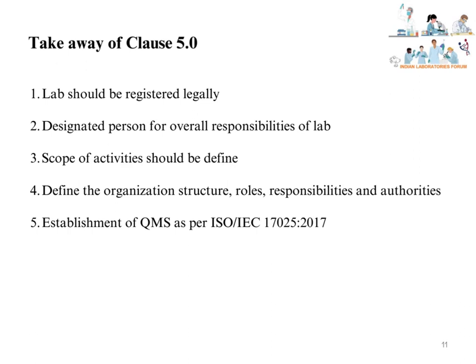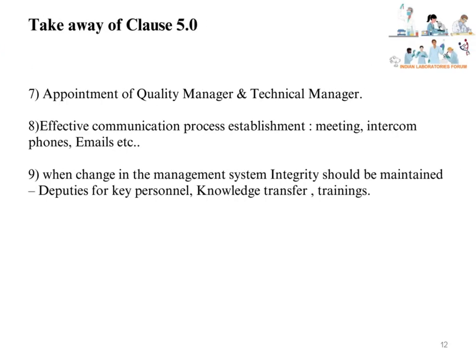Takeaways from Clause 5.0 of ISO IEC 17025:2017: The lab should be registered legally. The lab should have a designated person for overall responsibilities. The scope of activities should be defined. The organization's structure, roles, responsibilities, and authorities should be defined. Establish a QMS as per ISO IEC 17025:2017. The laboratory should appoint a quality manager for management system implementation and a technical manager for technical operations. Effective communication processes should be established through meetings, intercom phones, emails, etc. When there is a change in the management system, integrity should be maintained — for example, by having a deputy to key personnel.